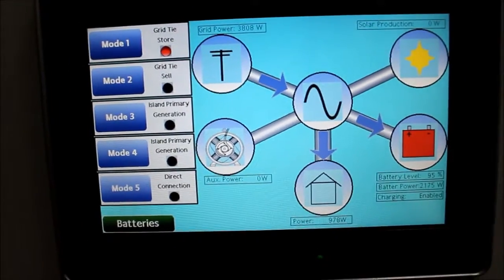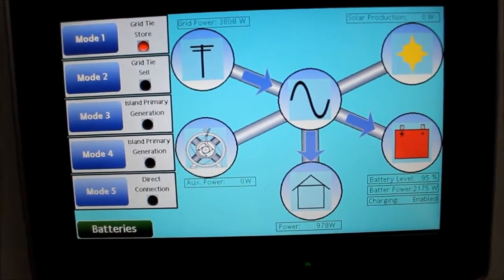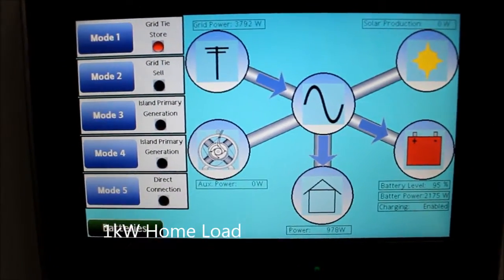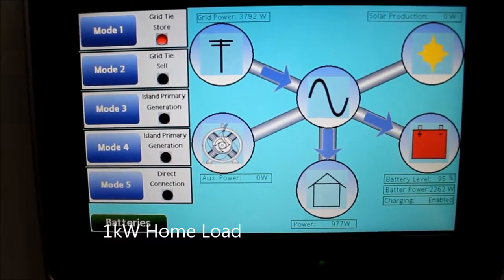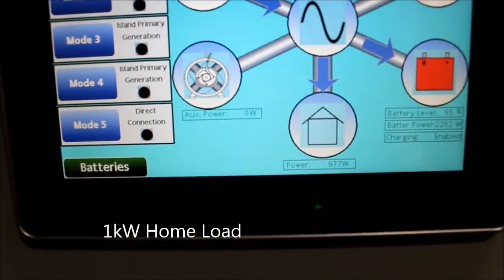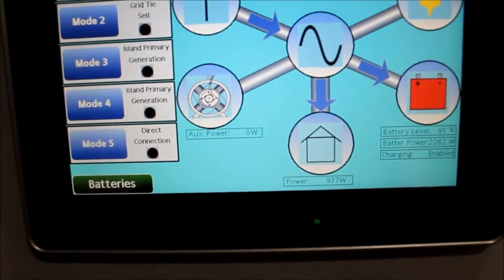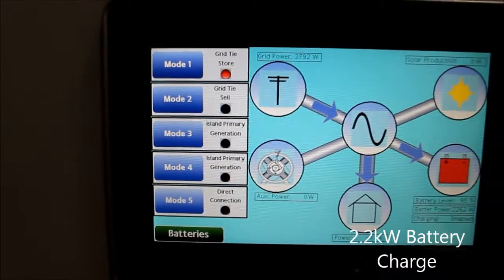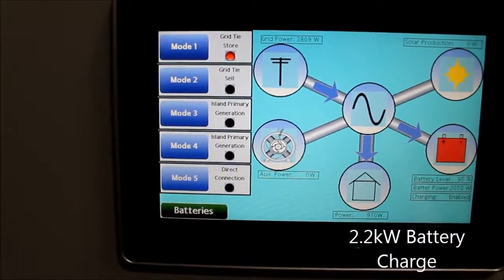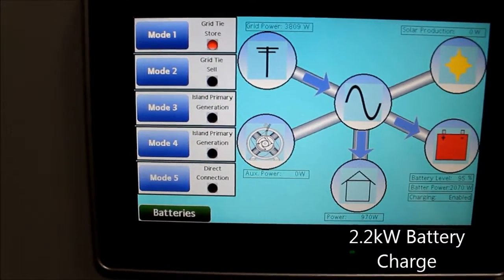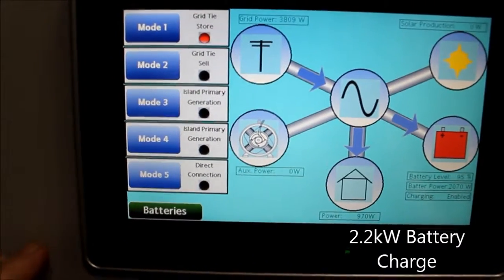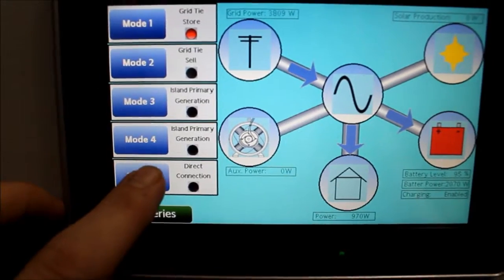Right now the batteries are being topped off. They went below their preset limit on charge level, so they are being topped off. We are serving about 1,000 watts to the home, and the system is in mode 1. I'm going to put the system into mode 5 via the HMI interface.